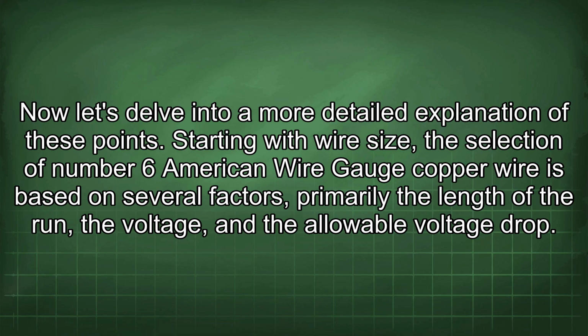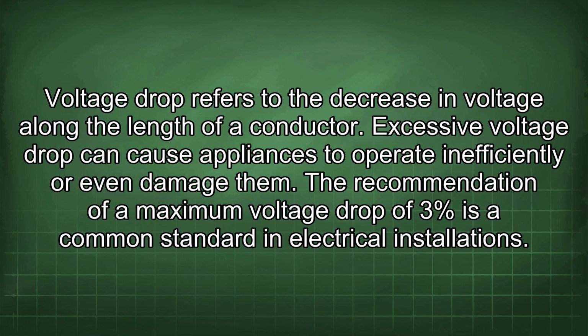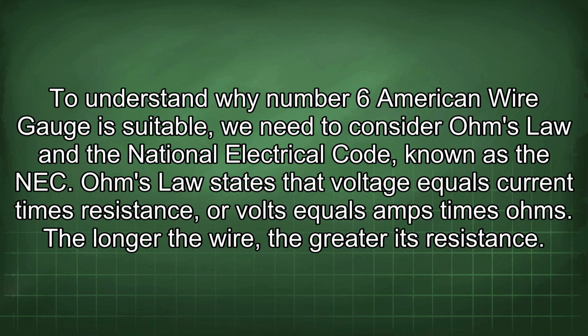Starting with wire size, the selection of number 6 American wire gauge copper wire is based on several factors, primarily the length of the run, the voltage, and the allowable voltage drop. Voltage drop refers to the decrease in voltage along the length of a conductor. Excessive voltage drop can cause appliances to operate inefficiently or even damage them. The recommendation of a maximum voltage drop of 3% is a common standard in electrical installations. To understand why number 6 American wire gauge is suitable, we need to consider Ohm's law and the National Electrical Code, known as the NEC.